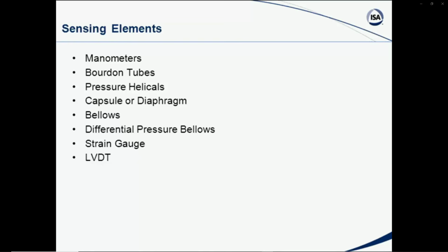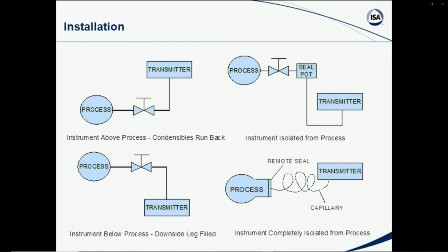And we will be focusing primarily on transmitters, which use some sort of a capsule or a diaphragm. It's a small movement that is obtained by having a pressure on one side and using the plates of the diaphragm as a capacitor, and changing the capacitance as the pressure goes up and drops off. In fact, all pressure measurements are a differential pressure. You're either comparing a pressure to the atmosphere or atmospheric pressure, or you're comparing a pressure to some unknown pressure, like in a level or a flow measurement or something along that line. So all pressure measurement is actually a differential pressure measurement, and we need to keep that part in mind too.